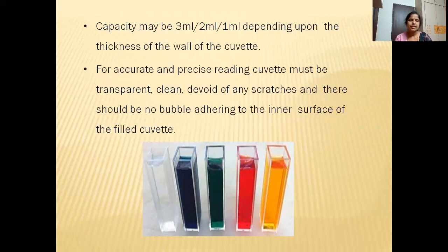You can see these are cuvettes filled with solutions, and always see that the solution is filled only up to 3/4 of the cuvette. You have to hold it with your fingers touching the frosted sides, not the clear sides. For accurate and precise readings, the cuvette must be transparent, clean, without any scratches, and there should not be any air bubbles. So when you fill the cuvette with the solution, check that there are no air bubbles in it.